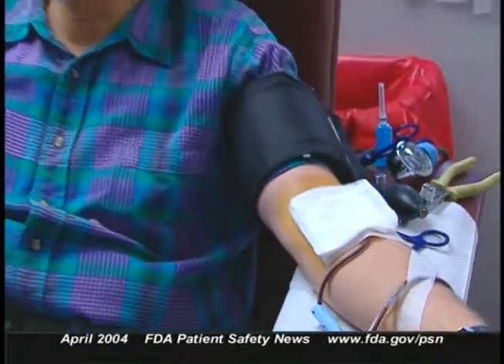Here's a report to share with colleagues in your blood banking facility. Ortho Clinical Diagnostics Incorporated has sent a letter to blood banks and other healthcare professionals alerting them to reports of false positive test results with the company's screening test and confirmatory test for hepatitis B antibody. These tests are used by blood banks to screen blood donors. Over the last several months, some donors may have been notified that they had a positive hepatitis test because of these false positives. The company is still doing an investigation and doesn't yet have the cause pinpointed.